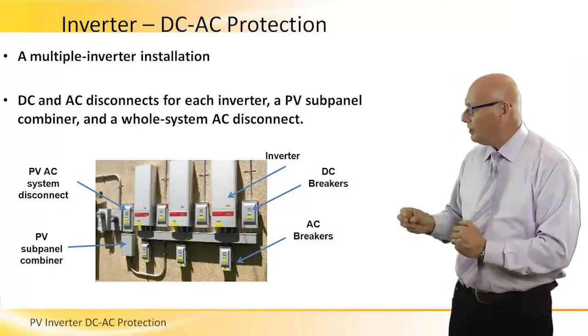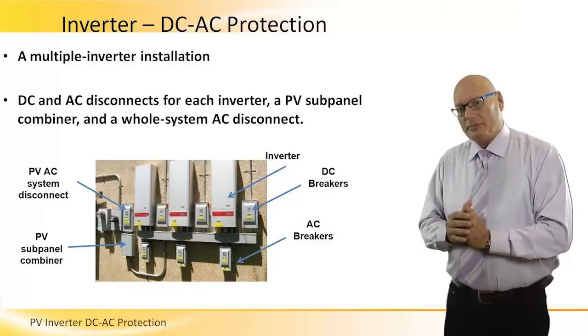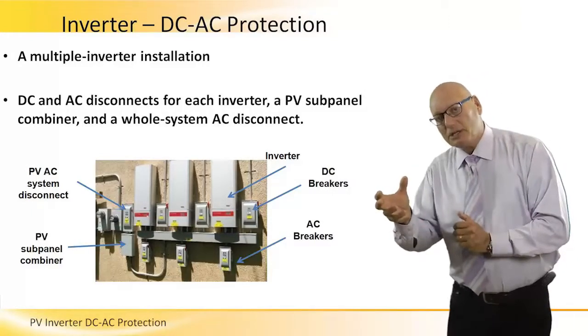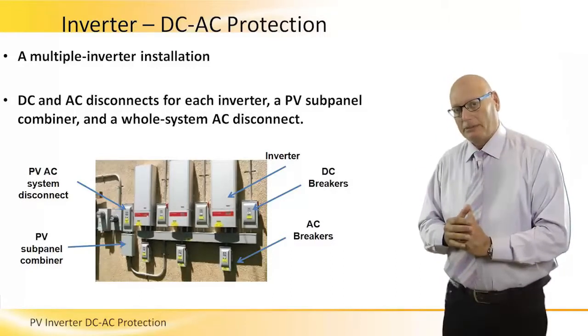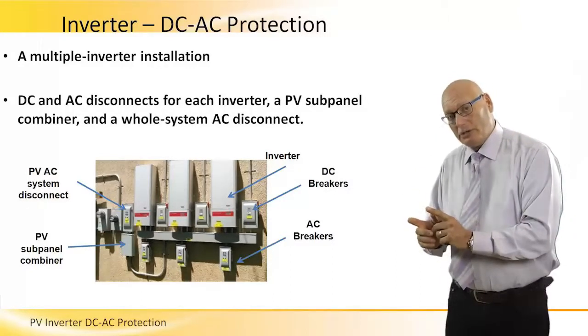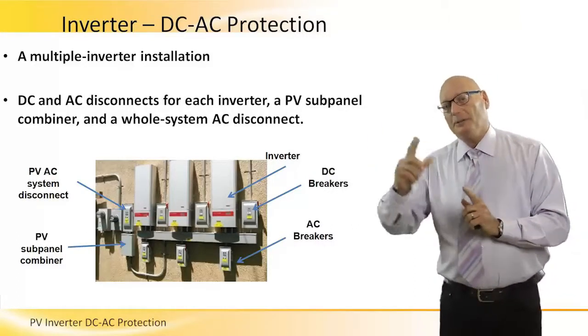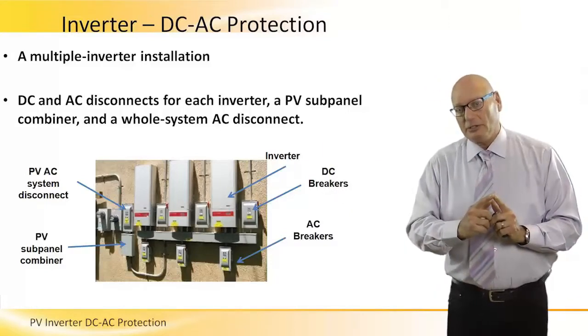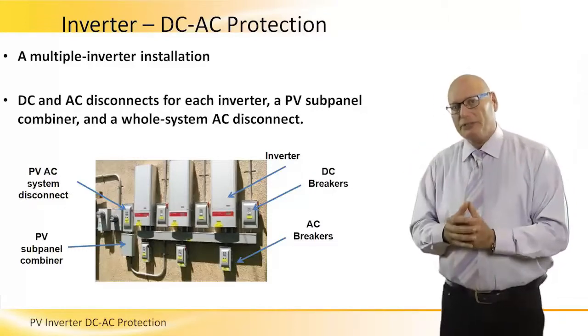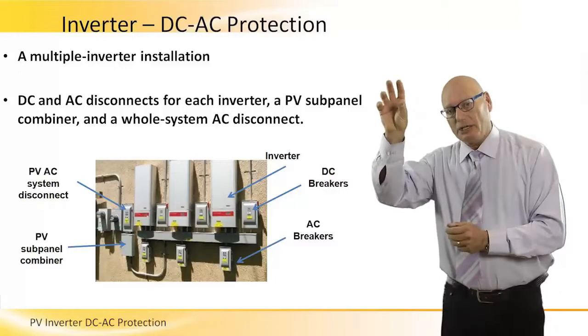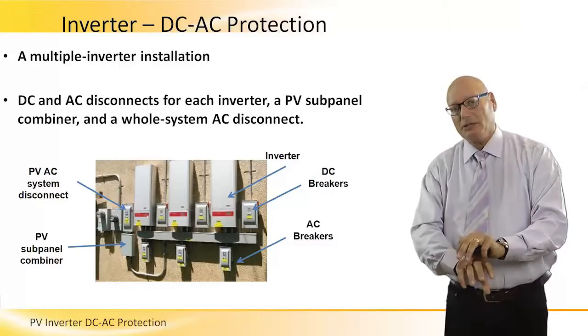On the bottom side of the bus, we see three AC breakers. Each inverter has a DC breaker right next to it and an AC breaker right next to it. The distances are centimeters. That's because, like we said before, the distance between the PV array and the inverter is longer than 10 meters. So we have a DC switch right on the inverter — we have one up on the roof right next to the array, but also one here right next to the inverter. And again, AC right after the inverter.